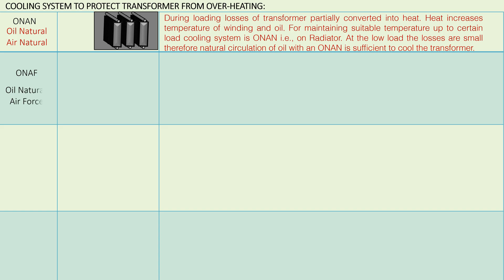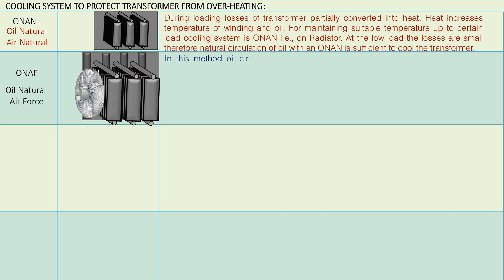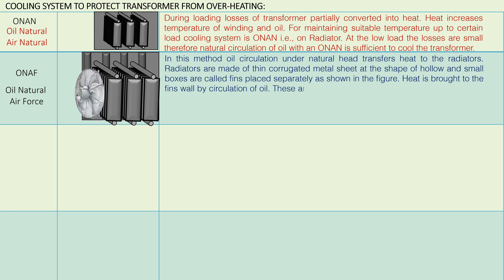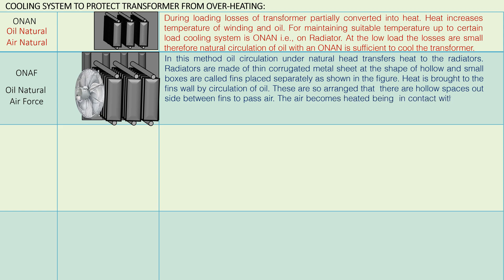ONAF — Oil Natural Air Force: In this method, oil circulation under natural head transfers heat to the radiators. Radiators are made of thin corrugated metal sheet with a shape of hollow small boxes. Heat is brought to the fin walls by circulation of oil; these are arranged so there are hollow spaces between fins to pass air. The air becomes heated being in contact with hot fin walls, and the hot air is removed to allow fresh cool air by using an air blast produced by fans. Fans start at 65 degrees Centigrade.